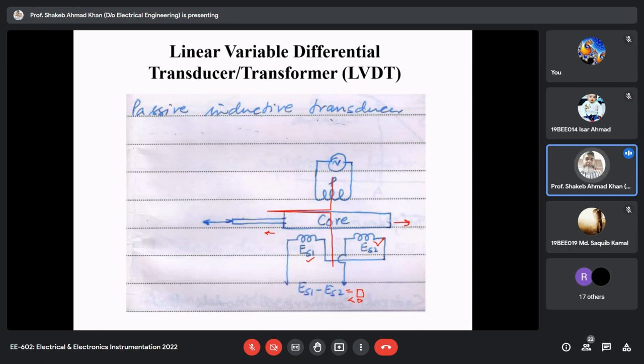Now, the other way around, if the core moves in the other direction from the reference position, the flux linkage of this coil will increase compared to the other, so ES1 becomes greater than ES2, and the output voltage becomes finite and positive. So whatever displacement we want to measure, we displace the core from the reference position and get output accordingly.